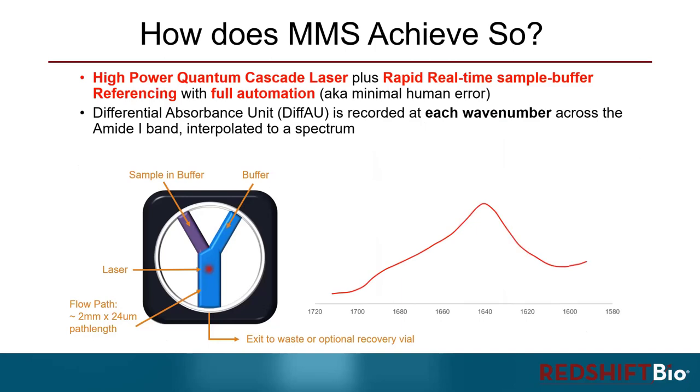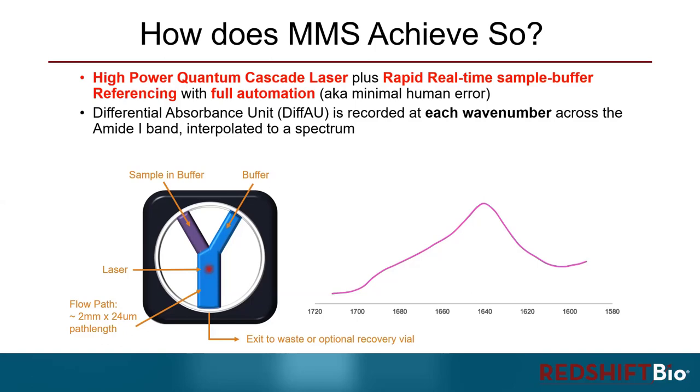By rapidly alternating the sample and buffer through the flow path where the laser shines on, the differential absorbance unit, or the signal of the sample minus the signal of the buffer, is recorded at each wavenumber across the whole Amide I band of the IR spectrum, which probes the backbone conformation of a biomolecule and then interpolates it into a spectrum.